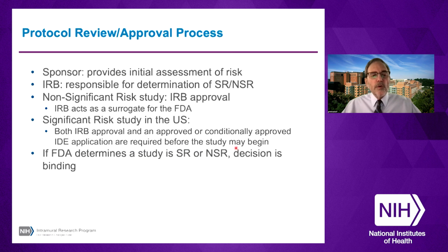So what's the protocol review approval process? You've gone through your checklist and you've determined that it is a device study, and now you need to figure out what level of control it is going to have. Is it going to be approved by the IRB or by the IRB and the FDA? So you as the sponsor or sponsor investigator, in developing your protocol, would provide a rationale for your initial assessment of risk.